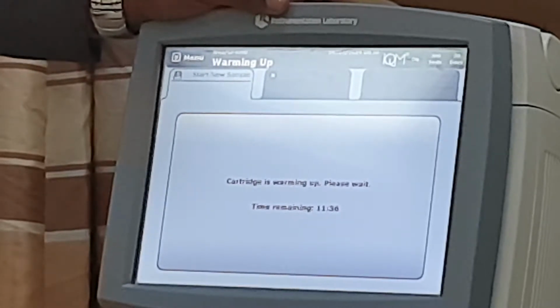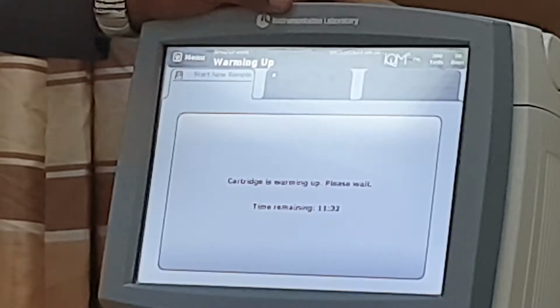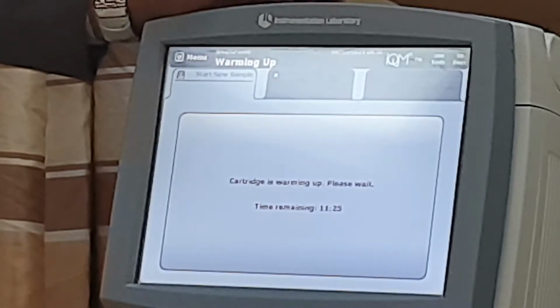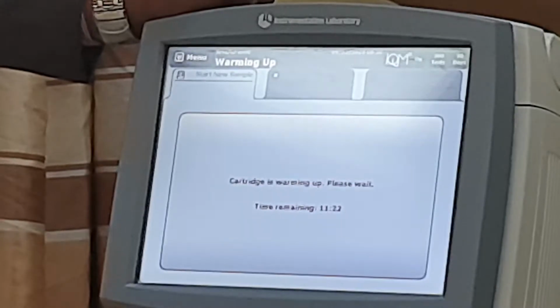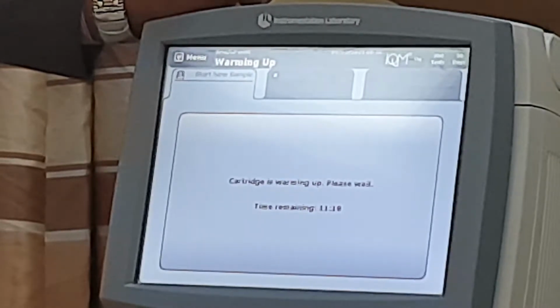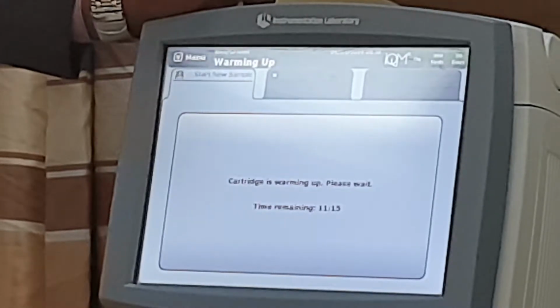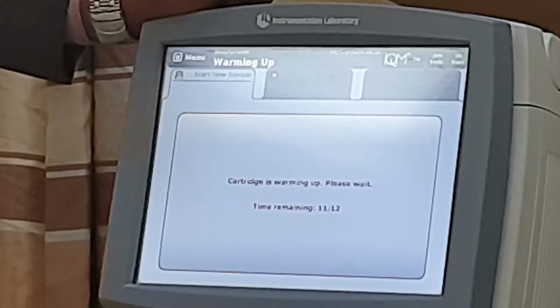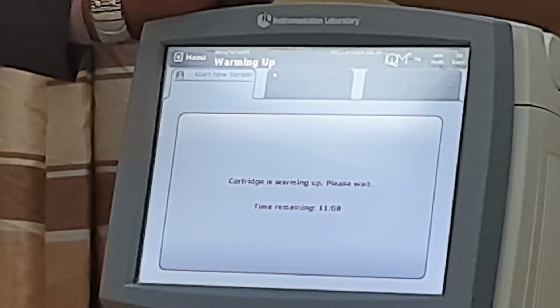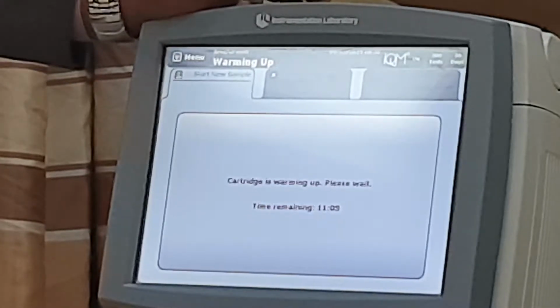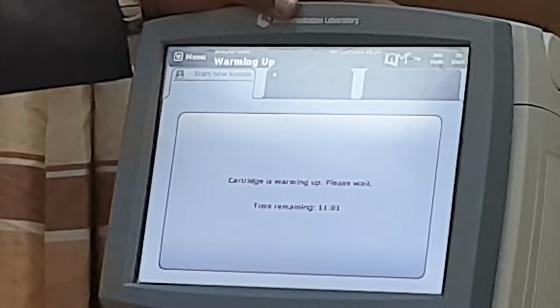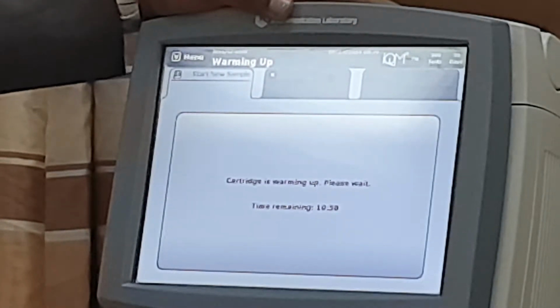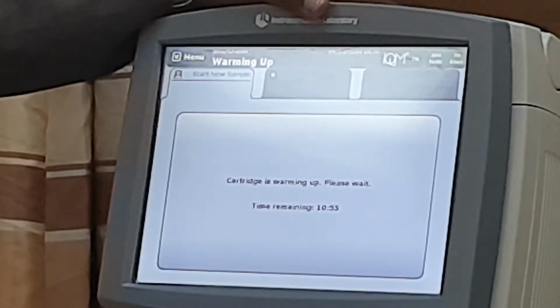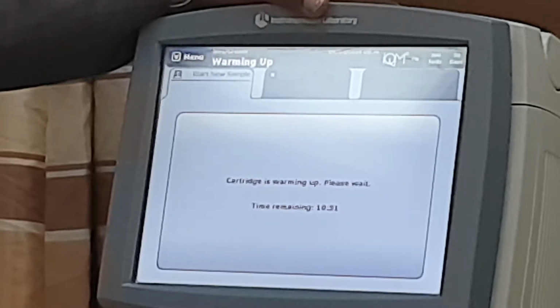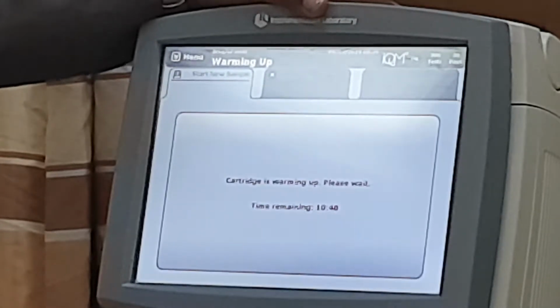Because one time maybe I will run one sample with an interfering material, for example benzalkonium, which is present in the catheter. There is something that causes interference in the catheter with sodium and potassium. Okay, I don't remember exactly, but there is an interference. Would it affect the sodium and potassium results? Yes, but the machine will run quality control after that sample to check if that parameter was affected or not. If it's affected, the machine will make the corrective action for you, and it will write it down also.